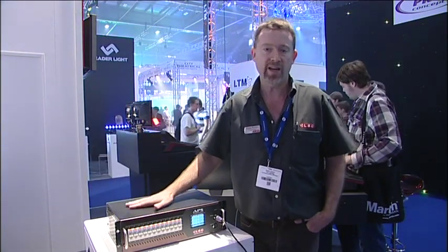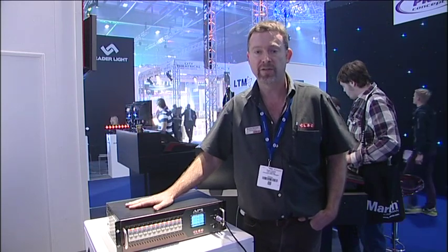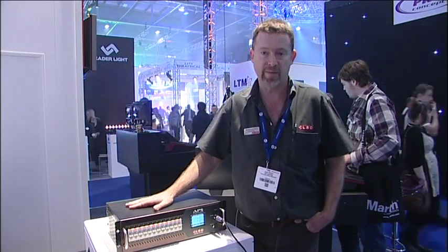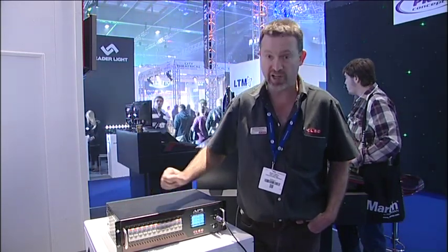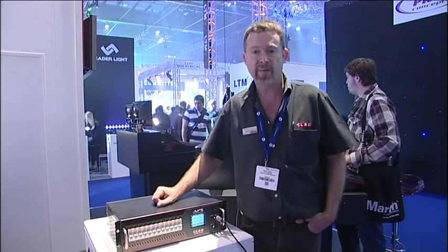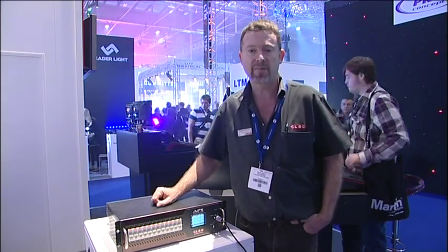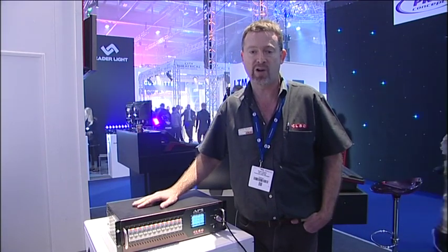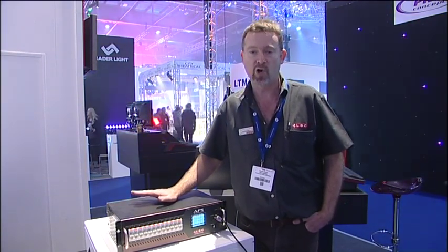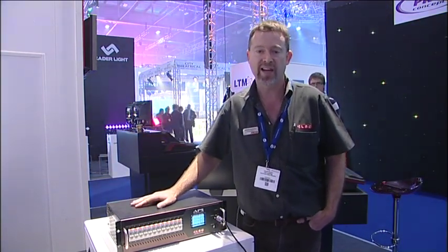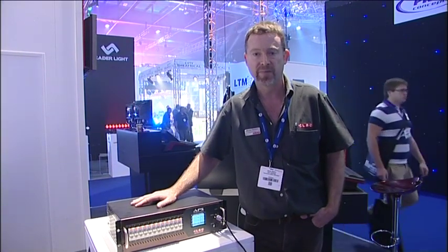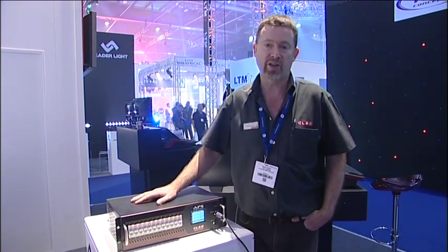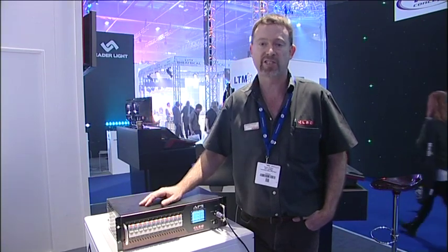Then, when the lighting console is turned off at the end of the show, the APS starts a countdown timer, which is programmable via the touchscreen user interface. If the DMX signal is not restored during this time, then the unit automatically powers down all the outputs, ensuring the rig is always turned off at the end of the show and energy consumption is kept to the minimum.